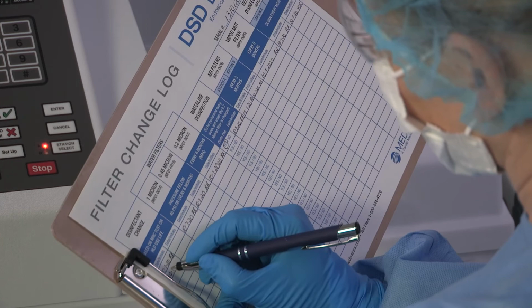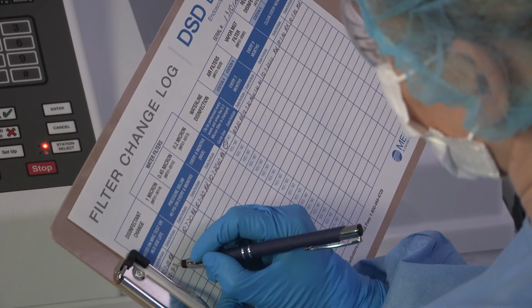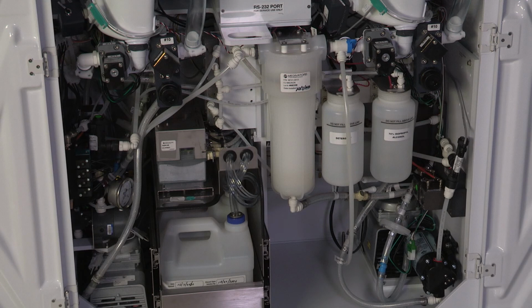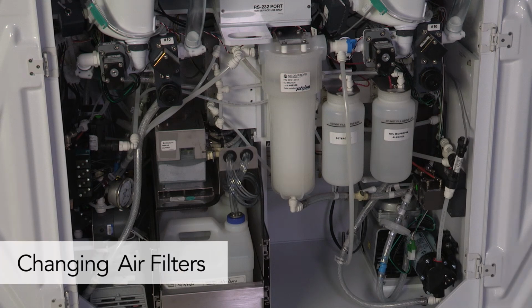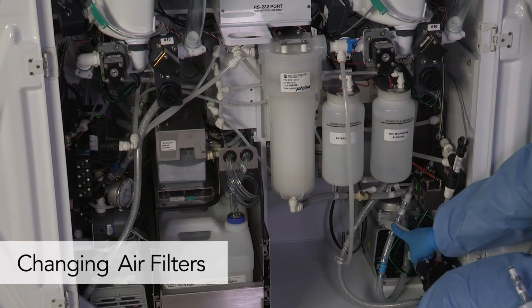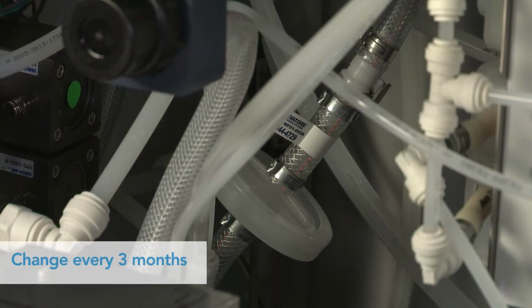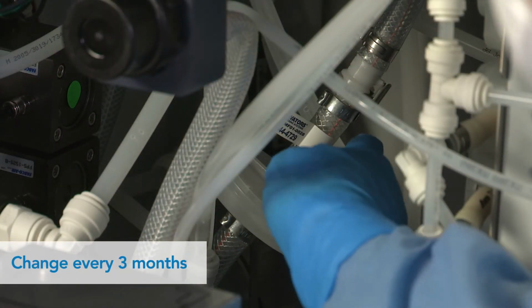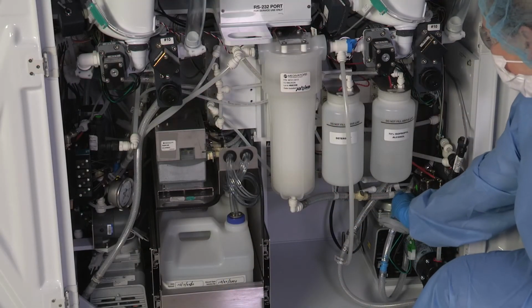Document cleaning both disinfectant filters on the filter change log. The DSD EDGE Reprocessor contains 2 air filters, one for each station. These filters should be changed every 3 months and are held in place by quick connect fittings. Let's start with Station B.